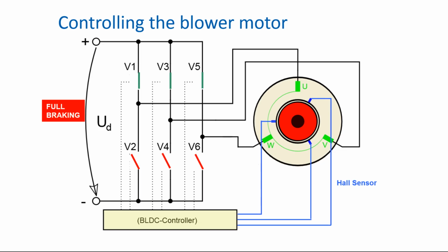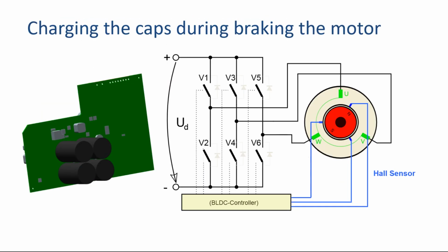When the motor needs to brake during the expiration phase, switches V1, V3 and V5 close, and V2, V4 and V6 open. This allows the current to flow from the motor back to the driver board. Four big capacitors located on the driver board store this energy that is generated by the motor. During startup and in the inspiration phase, the motor requires a lot of power. The energy stored in the capacitors helps speed up the blower immediately.